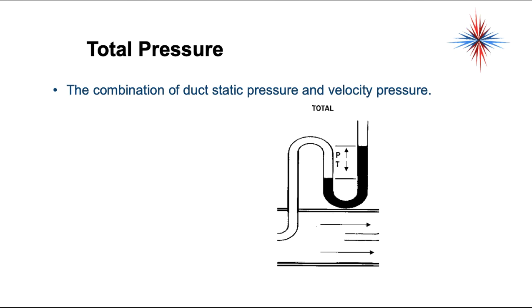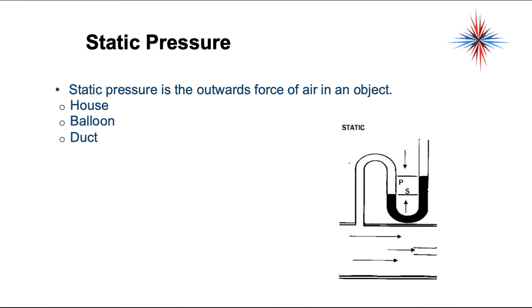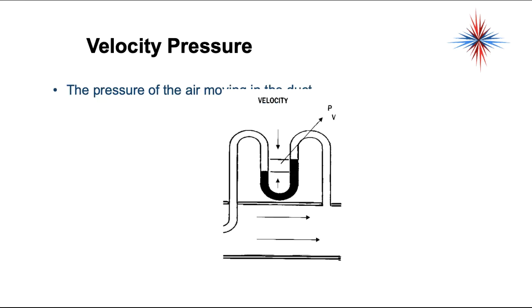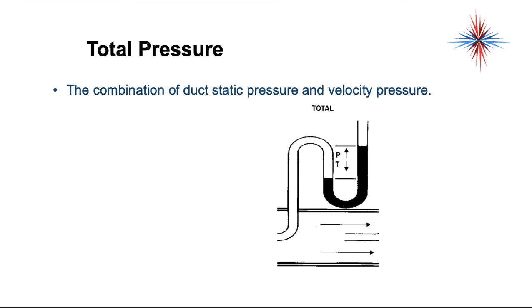Total static pressure is the combination of the duct static pressure and the velocity pressure. So we have three pressure readings: static pressure, which is the outward force; velocity pressure, which is the air moving inside the duct; and total pressure, which is the combination of duct static pressure and velocity pressure.